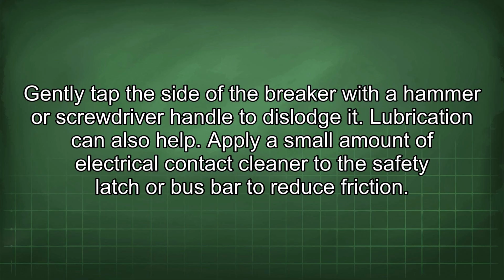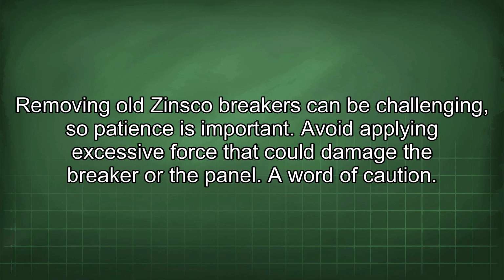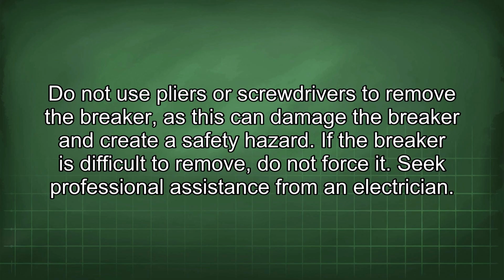Lubrication can also help. Apply a small amount of electrical contact cleaner to the safety latch or bus bar to reduce friction. Removing old Zinsco breakers can be challenging, so patience is important. Avoid applying excessive force that could damage the breaker or the panel. A word of caution: do not use pliers or screwdrivers to remove the breaker, as this can damage the breaker and create a safety hazard.